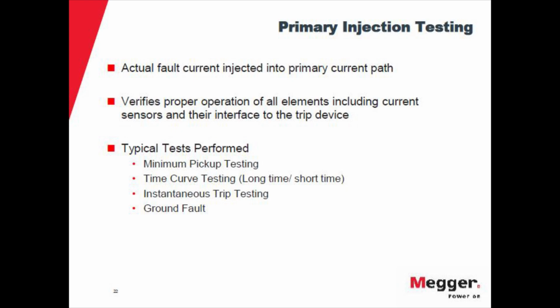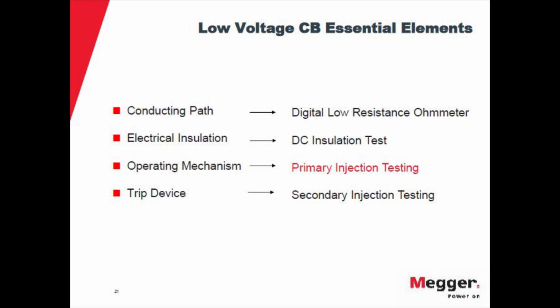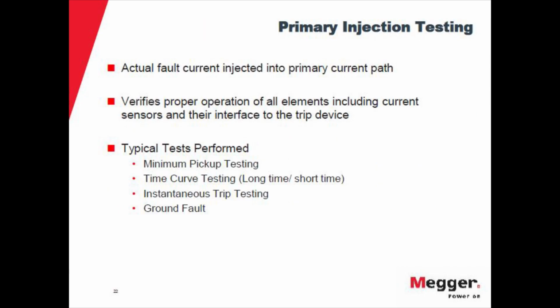Now, one thing in the low voltage breaker world: you have molded case circuit breakers, or you have air frame circuit breakers. In molded case circuit breakers, the trip device is not actually a device, it's more like an electromechanical actuating element, and you can't do secondary injection testing on those, so you have to use primary injection. We are talking about breakers that go from 5 amps to, I would say, 600 or 800 amps.